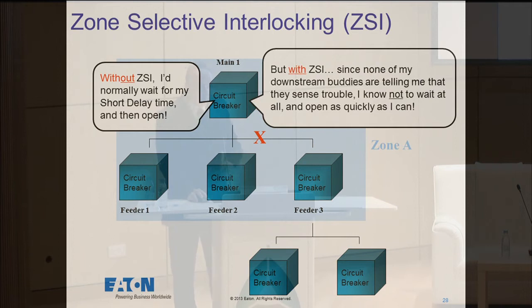So with ZSI, with zone selective interlocking, none of his downstream breakers are telling me that they sense problems, so he knows that it's somewhere in between the two. By doing that, he knows, I don't want to wait for my downstream breaker to pick it up. I want to go as fast as I can. So that's what he does. Through the communication, he says, I'm not going to wait for my short delay setting because I know the downstream one doesn't see anything. So I'm going to go as quickly as I can. I'm not going to wait.